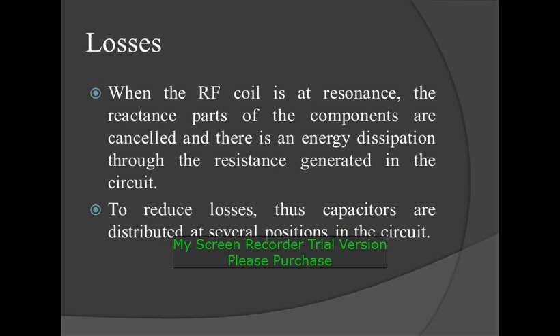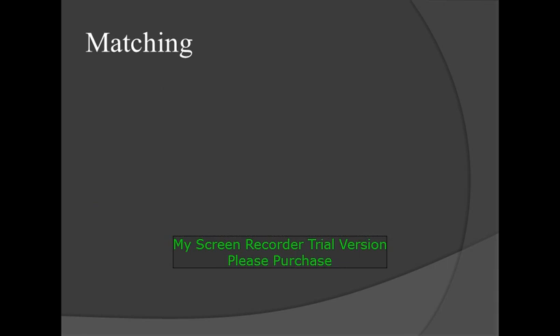Losses: when the RF coil is at resonance, the reactive parts of the components are cancelled and there is energy dissipation through the resistance generated in the circuit. To reduce losses, capacitors are distributed at several positions in the circuit.